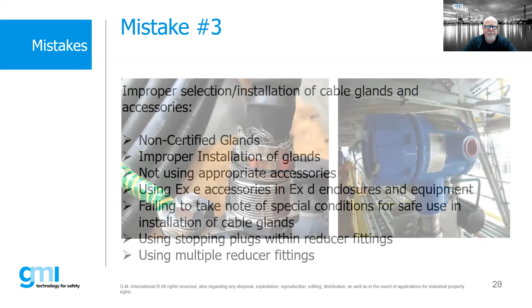When we look closer, doing detailed inspections inside cable glands, we see glands not installed properly, maybe the retaining ring not properly secured. In this case, what we're seeing is not necessarily a fault, but compression around the inner bedding, which is causing cold flow that could damage the cable. We need to be aware of these issues.